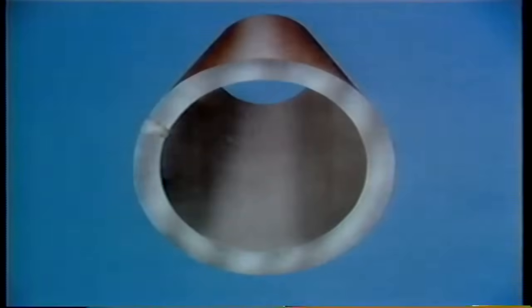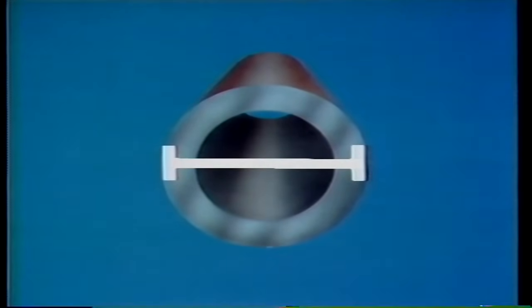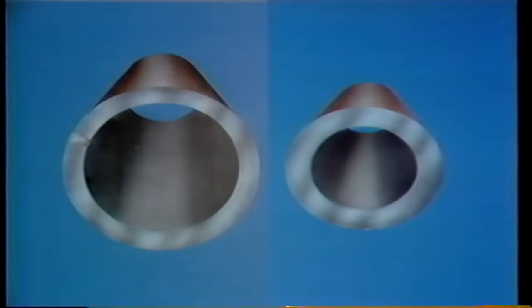Boiler tubes also usually have thicker walls than ordinary pipe. Another difference between pipes and tubes is the way their size is measured. Most pipe sizes are based on the inside diameter of the pipe. Tube sizes, on the other hand, are based on the outside diameter of the tube. So when the same size of pipe and tube are put side by side, it's obvious that there is quite a difference.